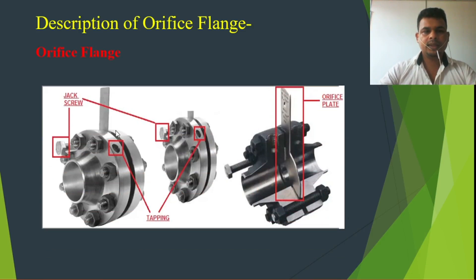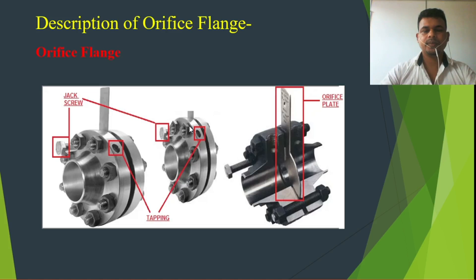You can see in another picture the tapping hole and the jack screw. The orifice plate sits in between the flanges. The jack screw is used to create a gap so the orifice plate can be removed easily for replacement or inspection.